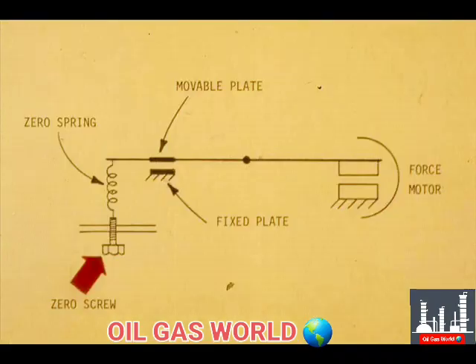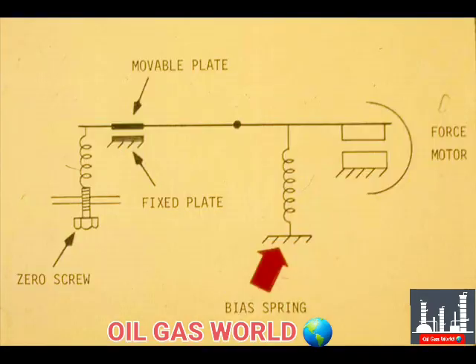A zero adjustment can be effected by using a zero spring and zero screw. By increasing or decreasing the spring tension, the output can be synchronized with the true level. The zero spring is opposed by a bias spring. The purpose of the bias spring is to pull the right end of the beam down when the force motor repulsion decreases.